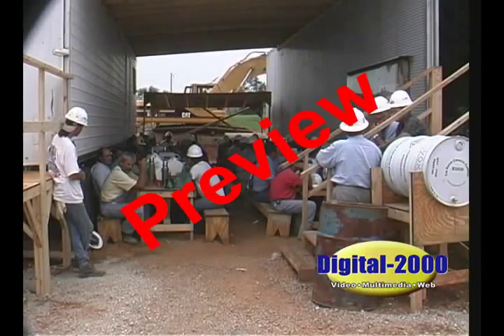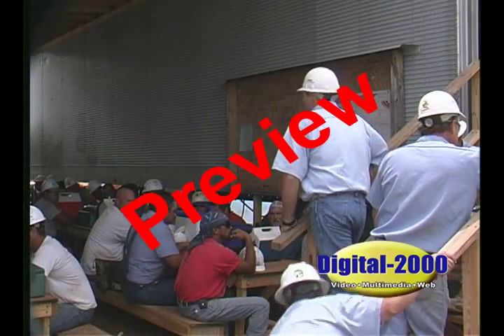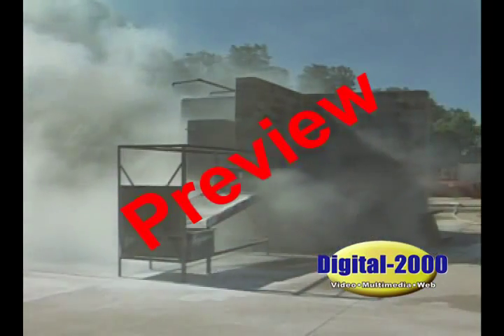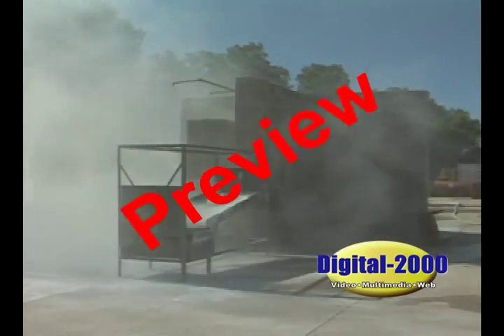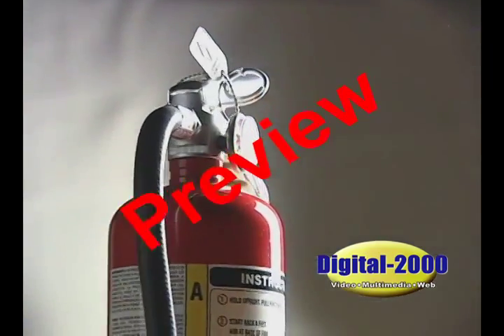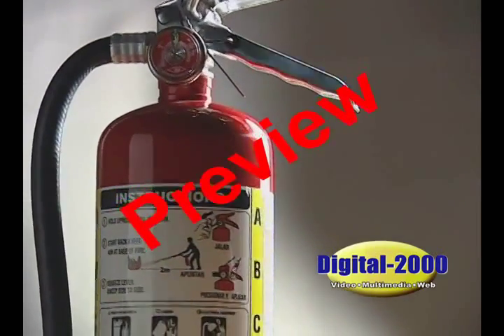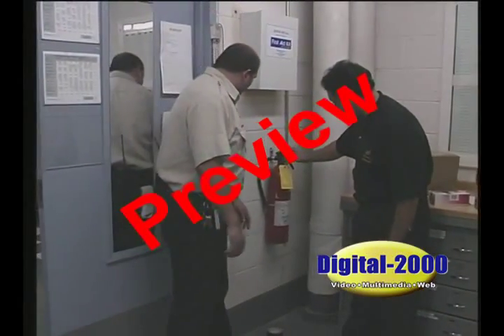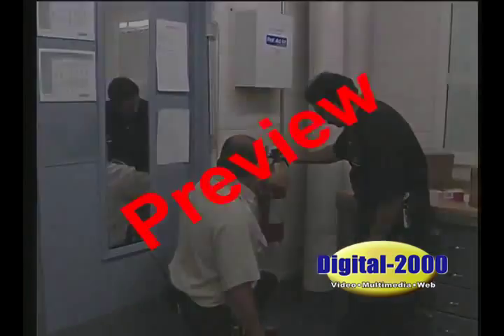A fire watch will be provided during and for at least 30 minutes after work and during any coffee or lunch breaks. Many times a fire will be slow to start, so the 30-minute time period will make sure a fire will not start up right after the work is completed. A fire watch is supplied with suitable extinguishers or appropriate extinguishing methods in the event there is a fire. Of course, the fire watch is trained in use of this equipment and in sounding the alarm in case of fire.